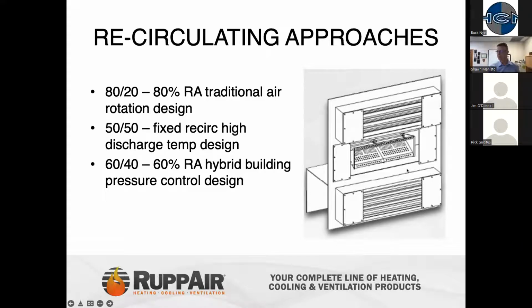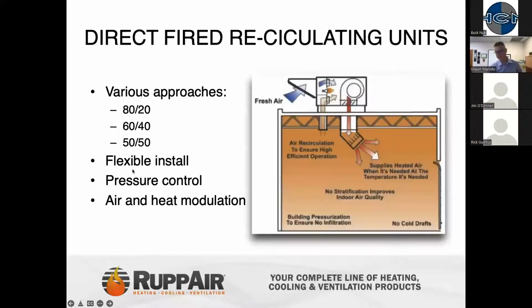In this case here, typically most manufacturers are still going to have their burner chamber designed for 20%, but they're going to fix a minimum of 30% additional across the fresh air and the balance of the 50% through the return air here. But in the 50-50 system, most commonly, those are going to be more like the 100% outside air heating systems that are on-off style systems, but have a fixed recirc position in a 50% outside, 50% return mode application. Then we get into what we refer to as a 60-40 system.